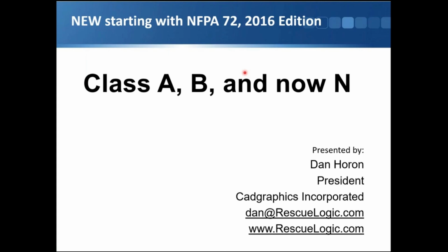Okay, so another subject is to talk about the Cat5 cable as it applies to fire alarm systems and its listing, as well as the NFPA's take on that. Is there a Cat5 fire alarm listed cable? As far as I know, there is not yet, but I know the wiring manufacturers have been talking about it. 2016 was kind of a beginning point where companies that make cable finally were able to say, yep, now we have to make it.